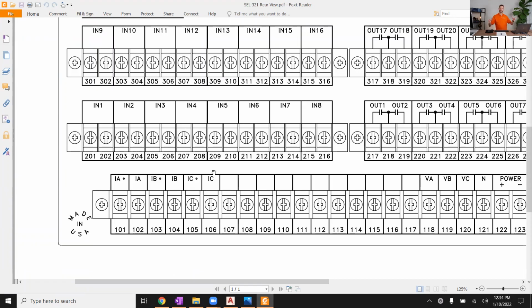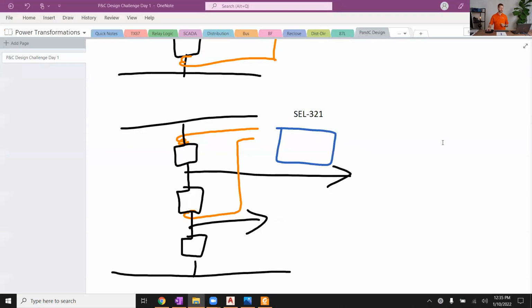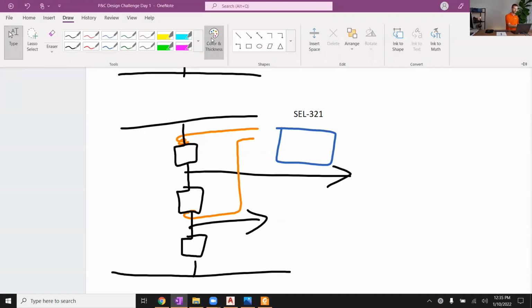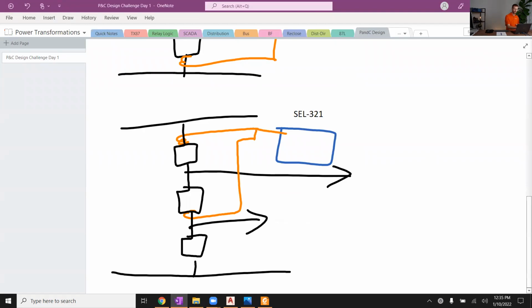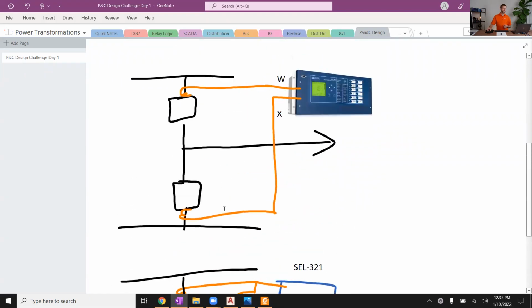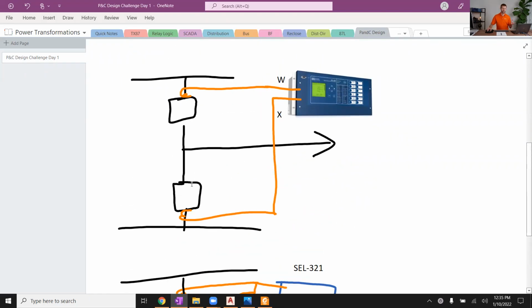I'm going to have to combine those 2 CTs external to the relay to parallel them to one another, and then wire in the combined line current quantity rather than the two separate breaker current quantities. So in that case, I would sum them up, parallel them external, and wire it in once to the current terminals. To answer your question, Hamad, breaker and a half, 3 breakers divided by 2 lines in the bay, 3/2, 1.5 breaker and a half terminology. So you can actually have 2 lines with 3 breakers rather than 2 lines needing 4 breakers if you needed a double bus, double breaker architecture.